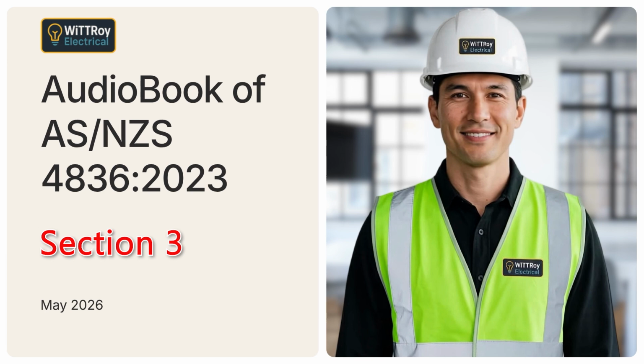Before work starts, test equipment must be checked to confirm that it is suitable and operating correctly. The correct test equipment must be used, and the correct operating range must be selected. Special care is needed when working with safety interlocks, control circuits, contactors, terminals, PLCs, and software interlocks. Bypassing, forcing, or bridging these systems can cause equipment to start unexpectedly or become energized unexpectedly.